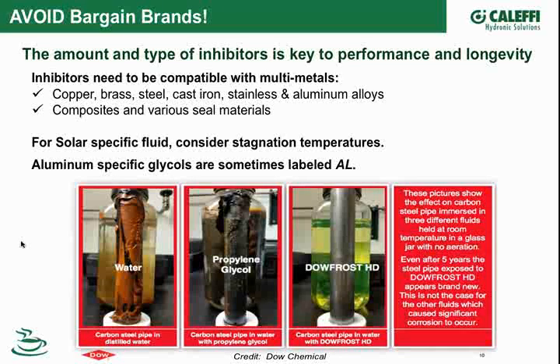This is where it's gotten really complicated in our industry. Back when I started in the plumbing business, we had cast iron boilers and copper tube, and that was pretty much it, some steel with the expansion tank, so three metals. It was a fairly simple system, but now as equipment efficiency goes up and manufacturers look for other materials to save cost or make things last longer, we've got stainless, aluminums with different alloys, and composites starting to show up. That presents a challenge for the people blending these fluids to cover a wide range, because what works for copper and cast iron might need to be blended differently for aluminum. Most products now have an AL label saying they're suitable for aluminum or aluminum alloys in the system.